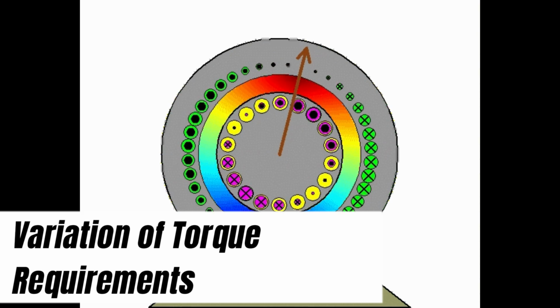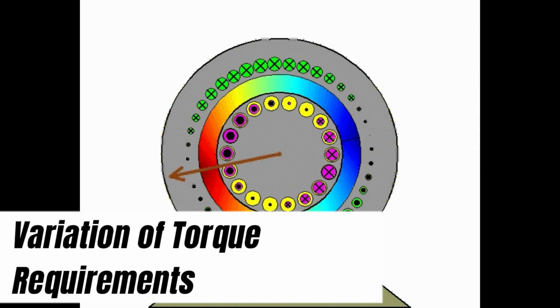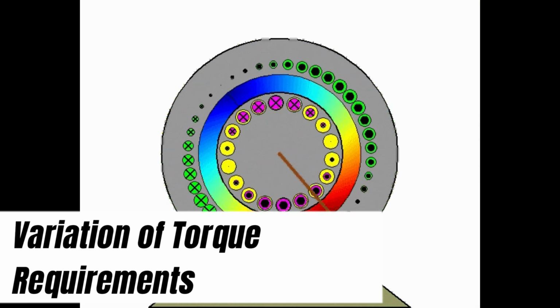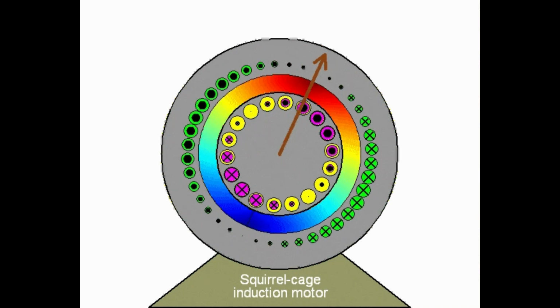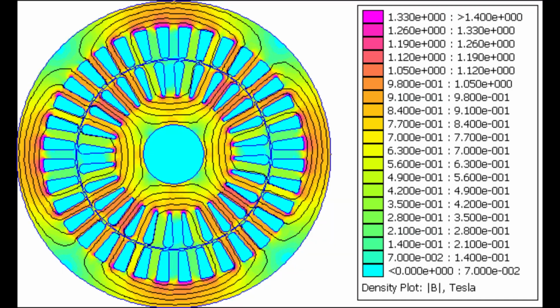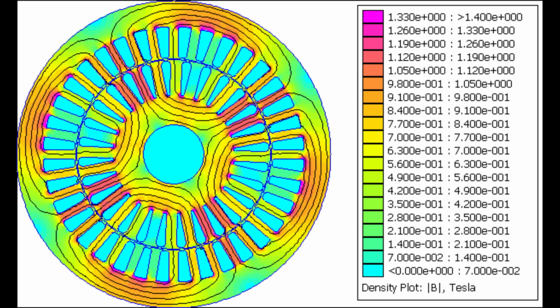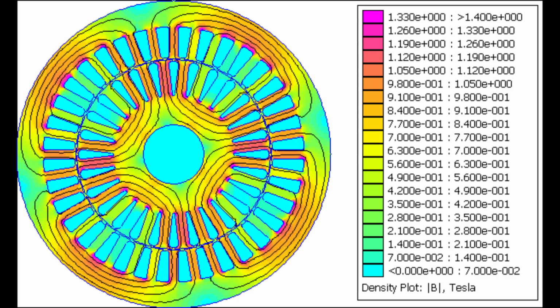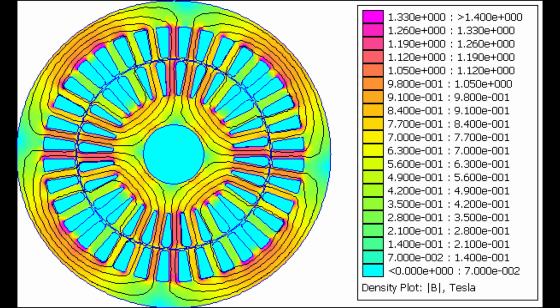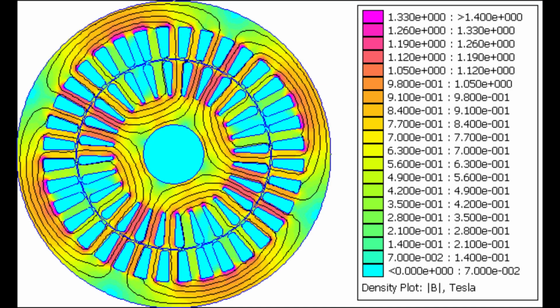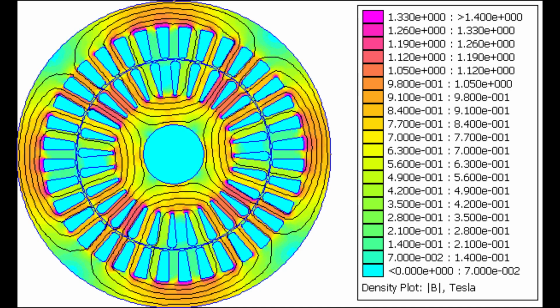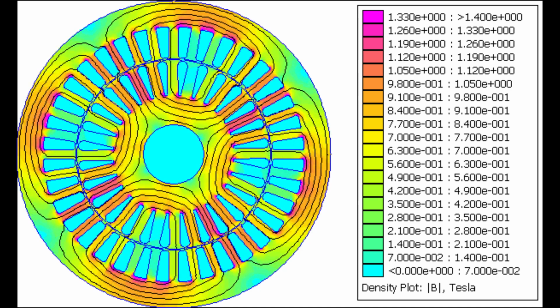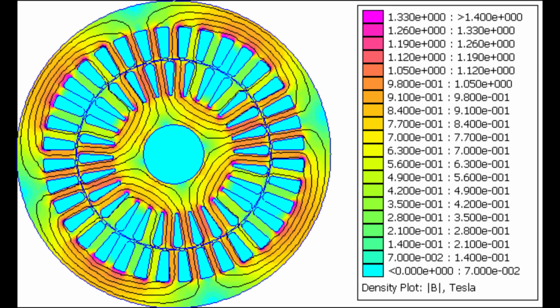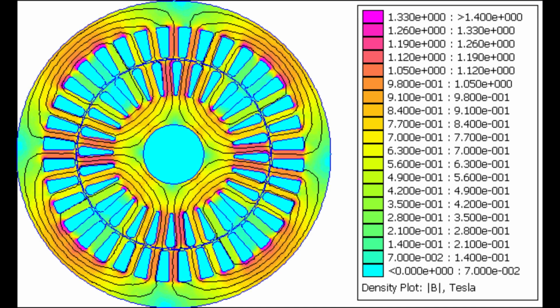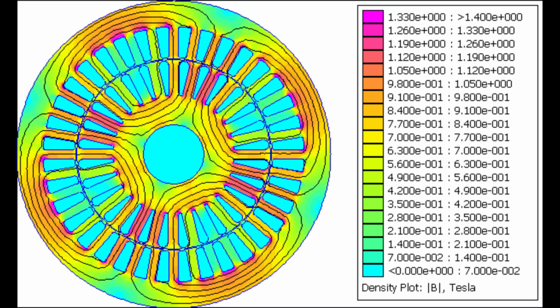Variation of torque requirements. Different loads have different torque requirements. This must be kept in mind when considering the starting torque required at the rate of acceleration most desirable for the load. In general, a number of motors will satisfy the load requirements of an installation under normal running conditions. However, it might be more difficult to use a motor that will perform satisfactorily during both starting and running. Often, it is necessary to decide which is the most important factor to consider for a particular application.